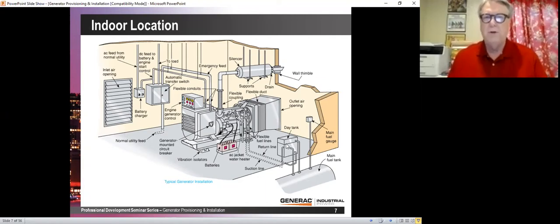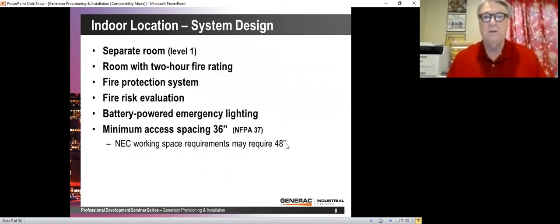So moral of the story, if you can put your generator outside, it's better, it's cheaper, you don't have to have a room, and all of these things are naturally taken care of by the manufacturer of the generator. However, if you really want your generator inside, we can certainly do that. Just be careful of the codes. And here's a manufacturer of a generator who put this in a standard, and it's kind of funny that it has several code violations.